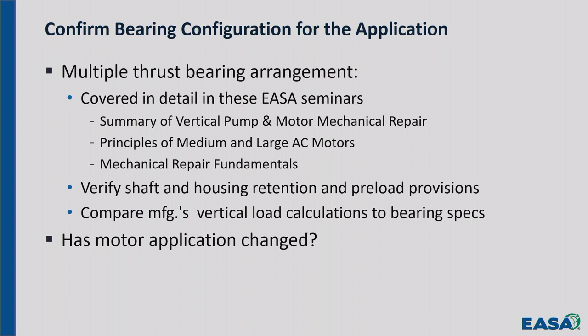Has the motor application been changed? That's one of the first questions you ask the customer if you've got problems with bearings. Did that the same pump that the motor came off of? We got a bunch of the pumps, they're all the same. Oh, no, they're probably not all the same, and that could be where your issue is.